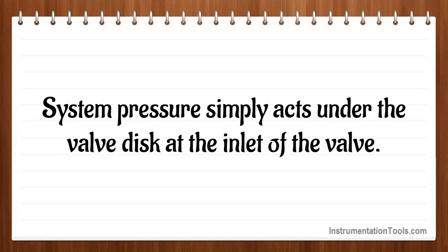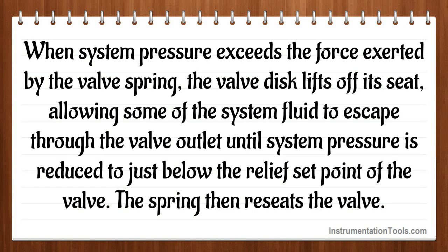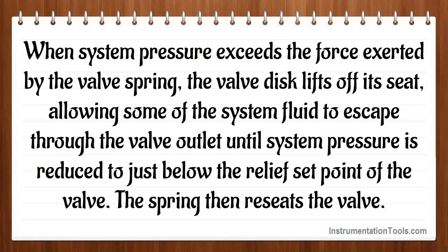System pressure simply acts under the valve disc at the inlet of the valve. When system pressure exceeds the force exerted by the valve spring, the valve disc lifts off its seat, allowing some of the system fluid to escape through the valve outlet until system pressure is reduced to just below the relief set point of the valve. The spring then reseats the valve.